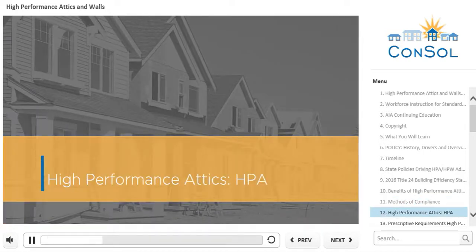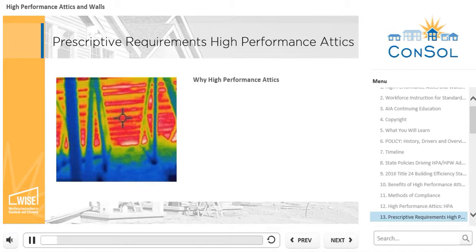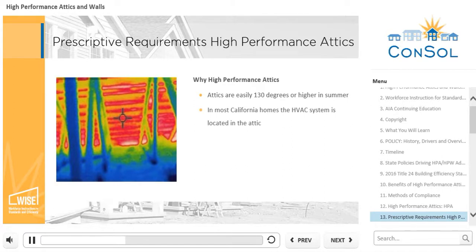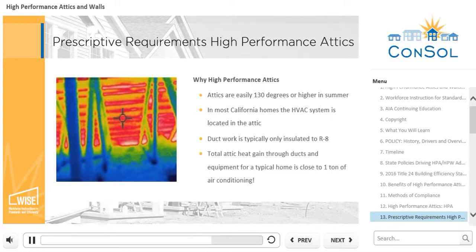Let's take a look at the specific requirements for high-performance attics. There are very good reasons for requiring the construction of high-performance attics. In the summer, attic temperatures are easily 130 degrees or higher. In most California homes, the HVAC system is located in the attic. In addition, ductwork is typically only insulated to R8. This leads to a total attic heat gain through ducts and equipment for a typical home of close to 1 ton of air conditioning.